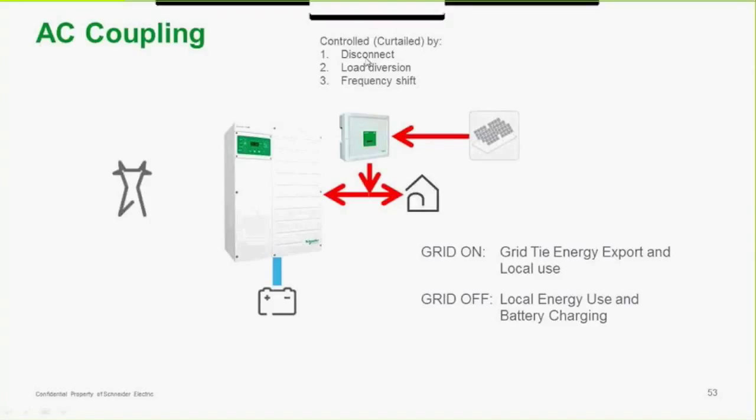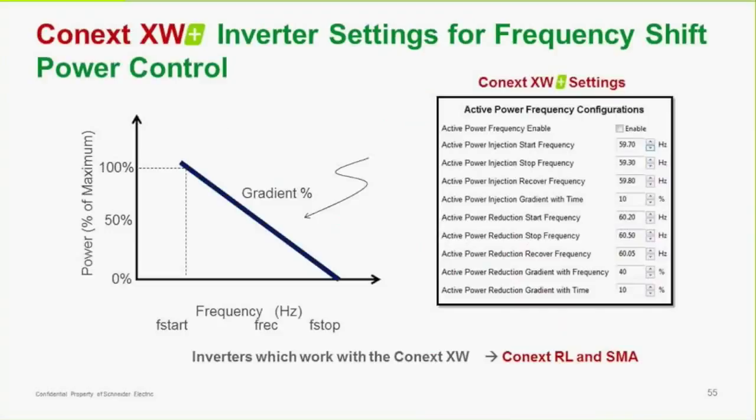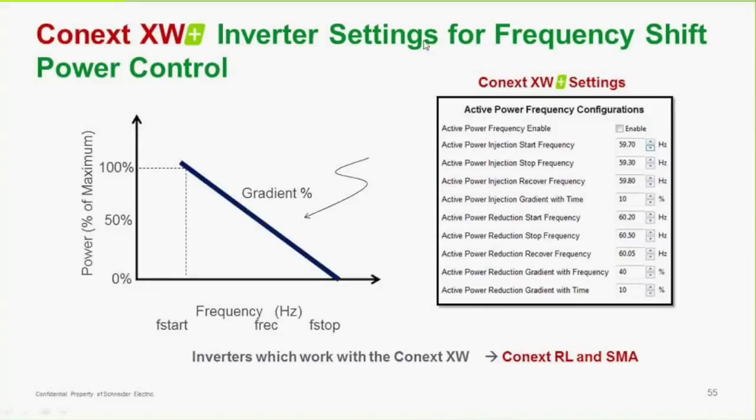Curtailment can be handled by disconnecting the inverter, or by load diversion where the power is directed to an additional load such as heating a driveway or dumping it. The third way — and the best way — is frequency shift. The XW Plus does provide frequency shift power control: as the power changes, so does the frequency, and as the frequency changes, that controls the grid-tied inverters. Once it goes out of range, the grid-tied inverter will shut down. Note that only one or two grid-tied inverters will work with the Conext XW+: our own Schneider grid-tied inverters or SMA grid-tied inverters.